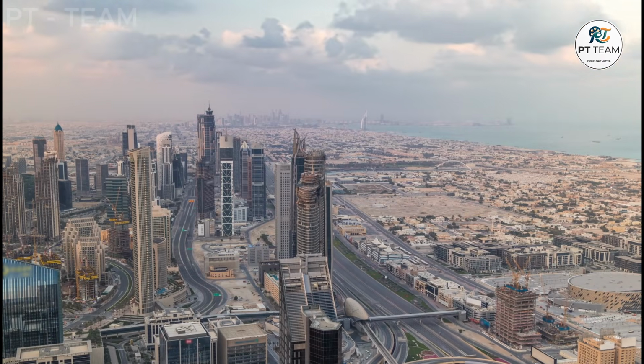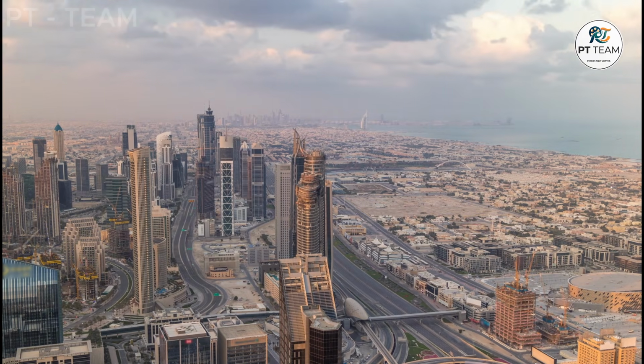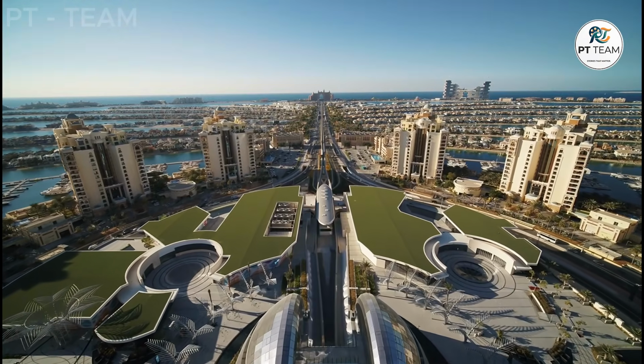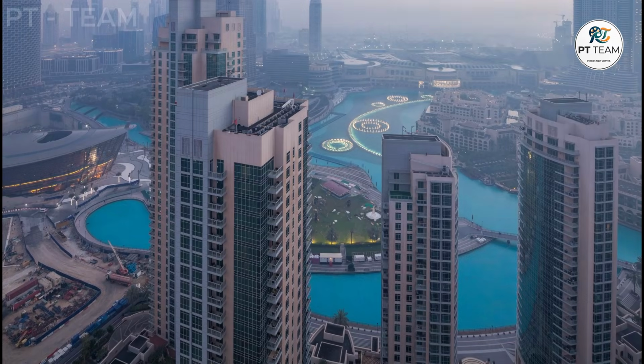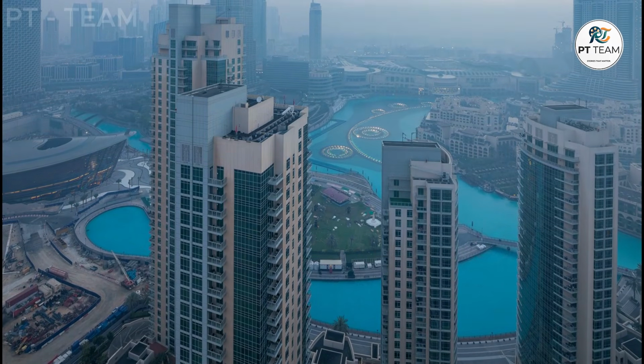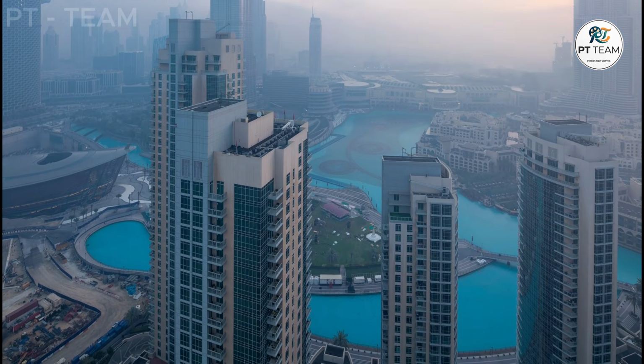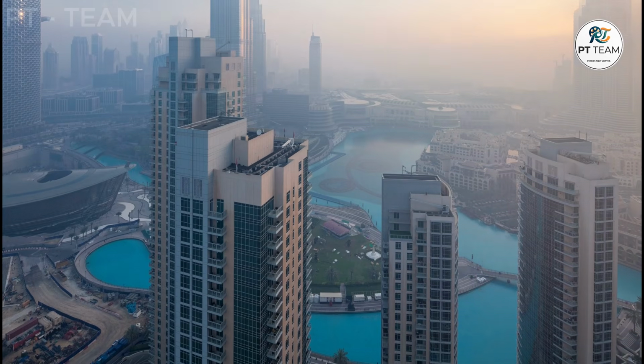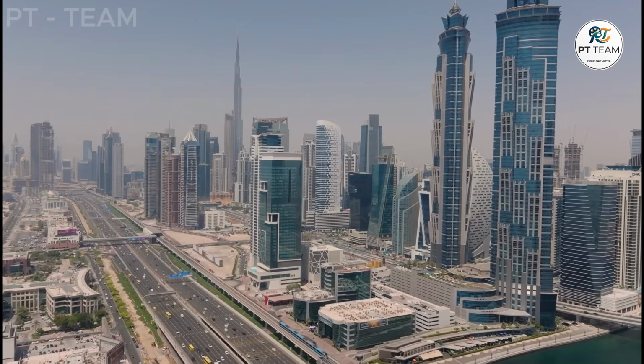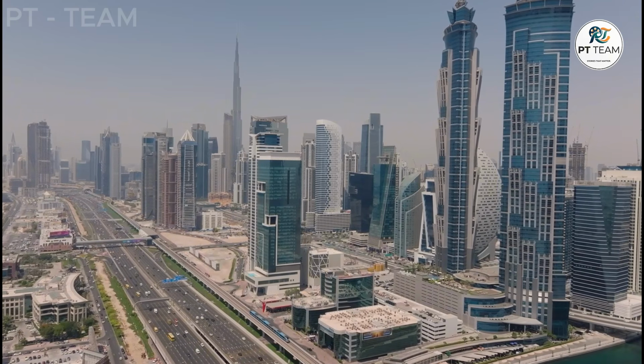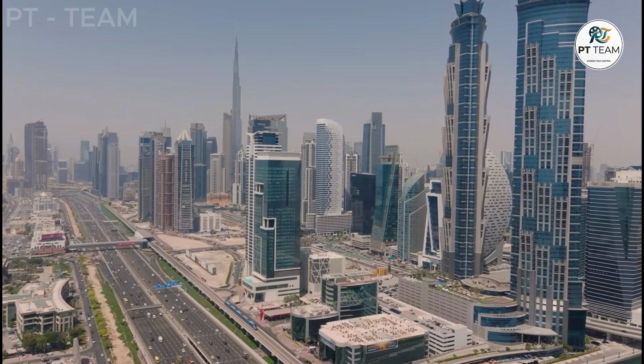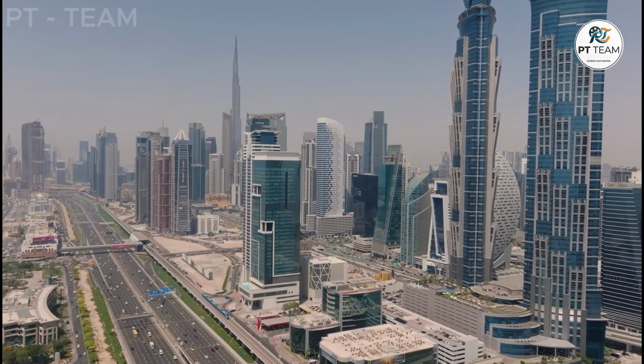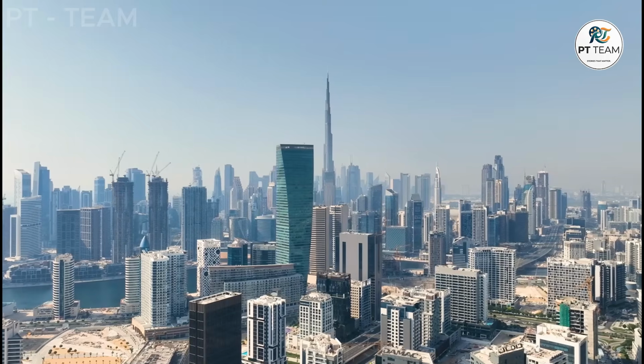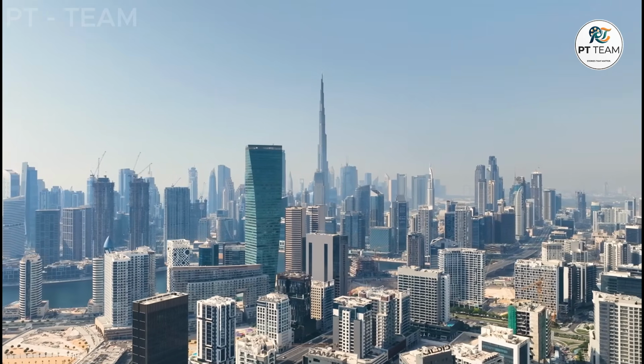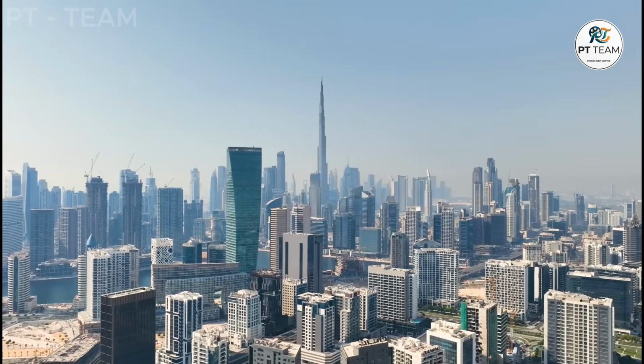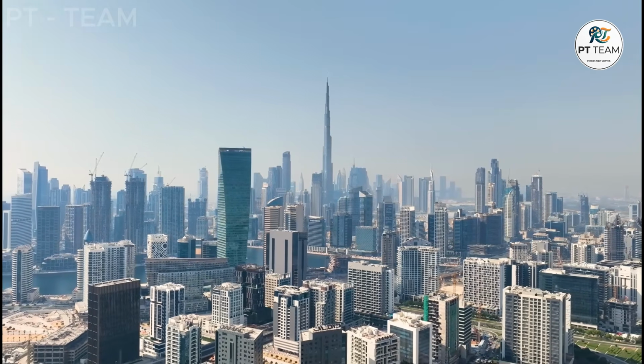Because reliable electricity and heavy machinery are not the only things hidden behind Dubai's seemingly infinite supply of cold air. To keep the central industrial chillers operating efficiently under immense pressure, the entire district system requires massive, continuous volumes of water. The outdoor cooling towers reject the city's collected heat, primarily through the process of evaporation, which means pure water is continuously leaving the closed system and vanishing into the hot atmosphere. That lost physical volume must be continuously replaced with fresh makeup water to keep the thermodynamics balanced.